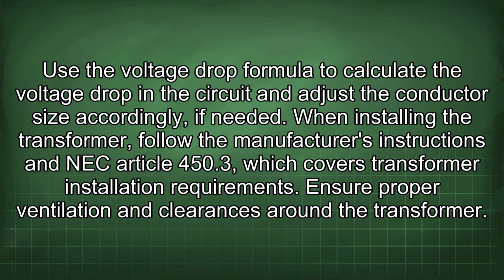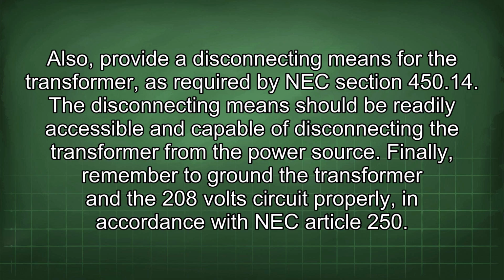Ensure proper ventilation and clearances around the transformer. Also, provide a disconnecting means for the transformer as required by NEC section 450.14. The disconnecting means should be readily accessible and capable of disconnecting the transformer from the power source.